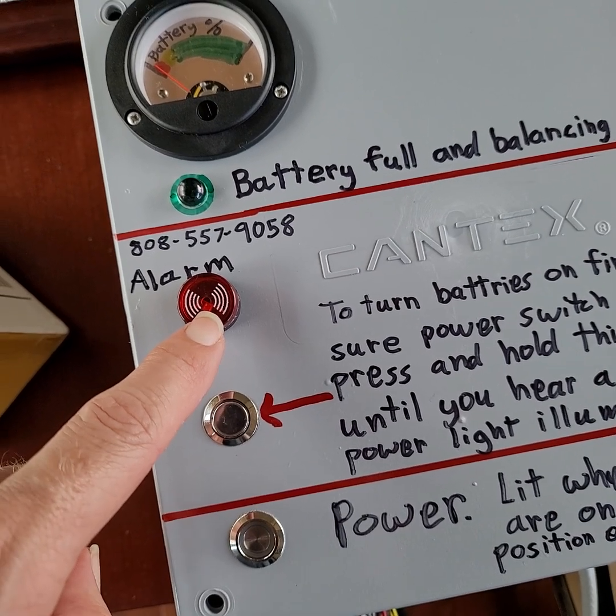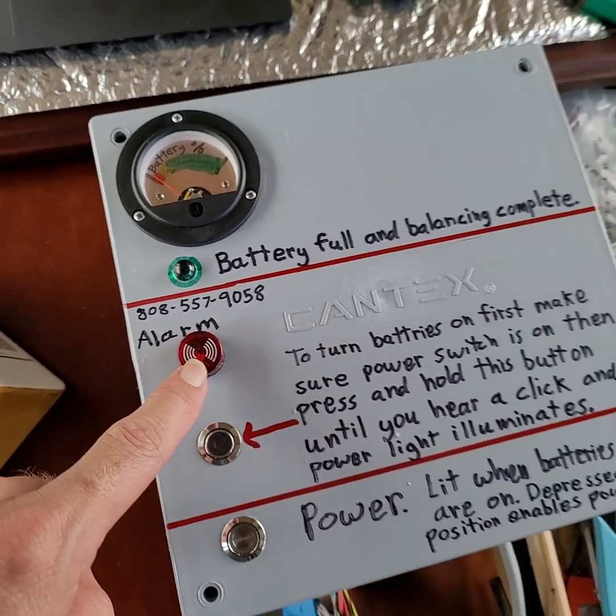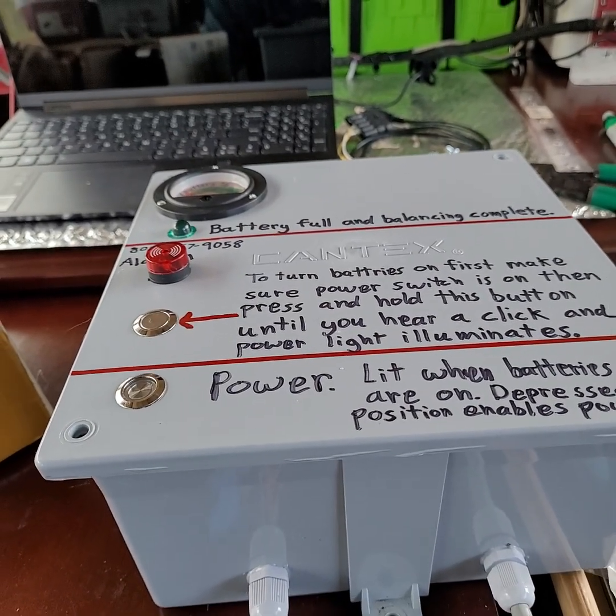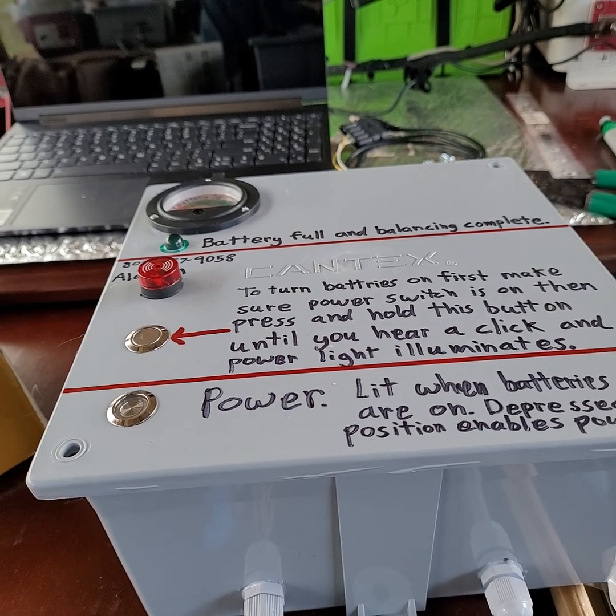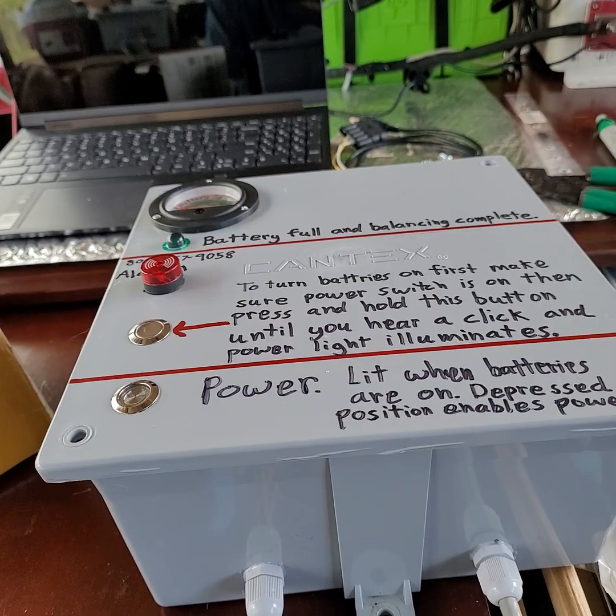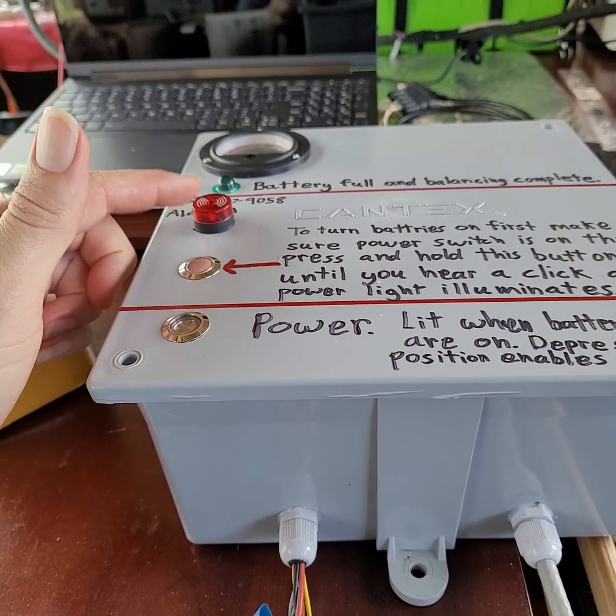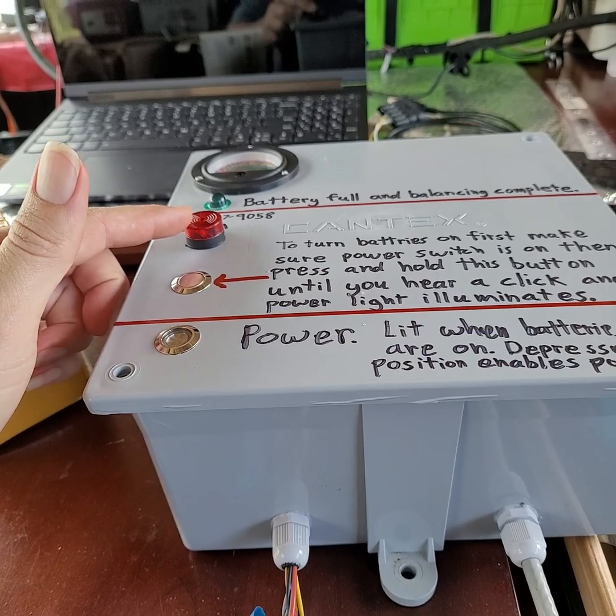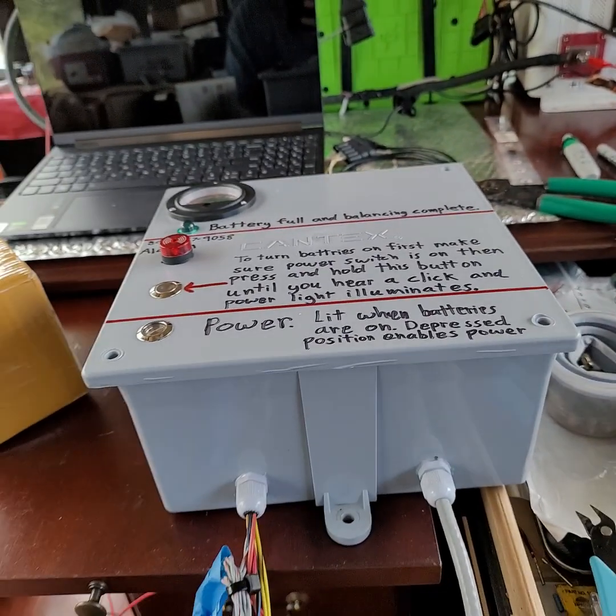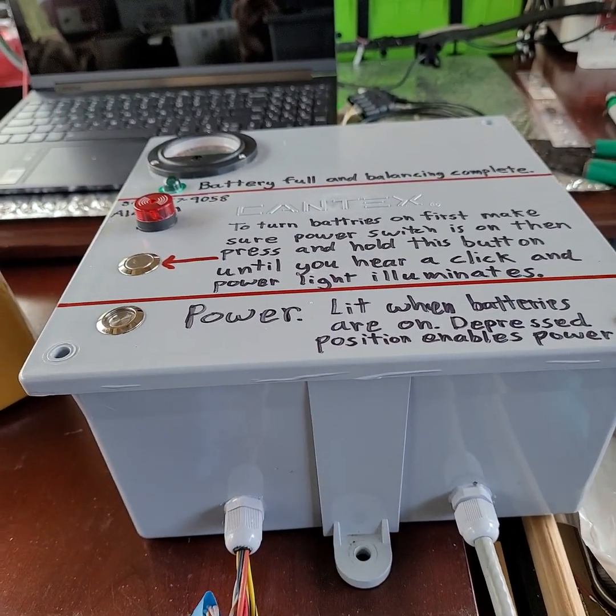If this alarm starts beeping or squealing and the red light is on, you have a problem. It could be over-current — unlikely — or over or under temperature, over-discharging, or overcharging. Things happen really fast when that alarm is on, so it's not going to give you a whole lot of warning before it actually shuts the system down. It'll turn the relay off, cut power to itself, and then it won't be squealing anymore.